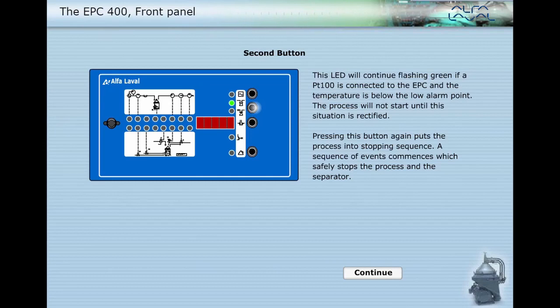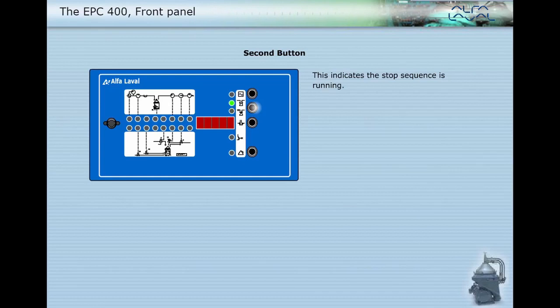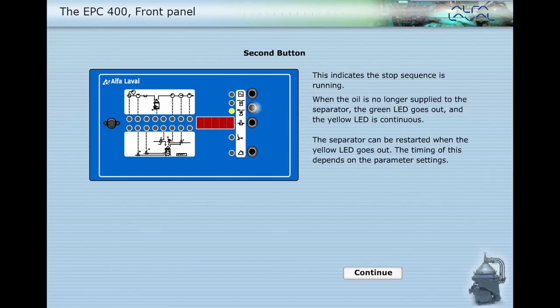Pressing this button again puts the process into stopping sequence. A sequence of events commences which safely stops the process and the separator. Click. This indicates the stop sequence is running. When the oil is no longer supplied to the separator, the green LED goes out and the yellow LED is continuous. The separator can be restarted when the yellow LED goes out. The timing of this depends on the parameter settings.